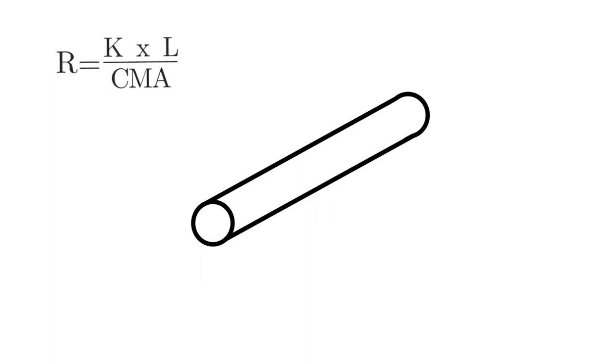When we're calculating out the resistance of a conductor, we can use this formula: R is equal to K times L over CMA. R is the resistance. K works out to be the constant of the natural resistance or the resistivity of the wire, depending on what the medium is, whether it's aluminum or copper would be the two most typical ones that we use.